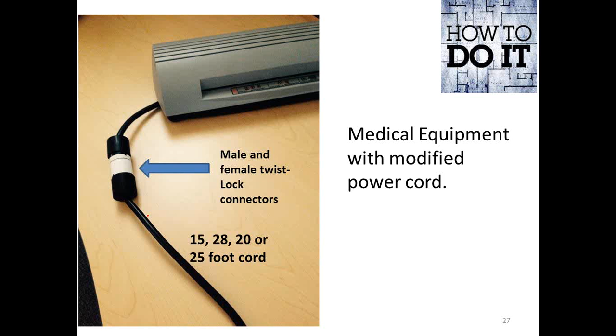Here's what it looks like. You have a piece of medical equipment up at the top, with a 6 to 10 foot original power cord. You need to put a 20-foot cord on it, so instead of going into the equipment, you add a male and female twist lock connector in line 6 inches from the unit, and then the one going to the wall to make it 15, 20, 50, 100 feet, whatever you need. You make it, you do it, you put it in.